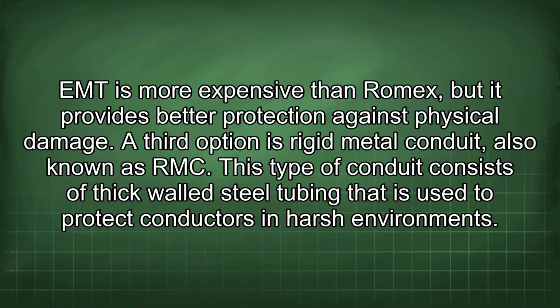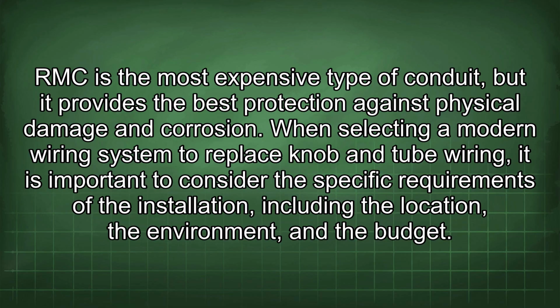A third option is rigid metal conduit, also known as RMC. This type of conduit consists of thick-walled steel tubing that is used to protect conductors in harsh environments. RMC is the most expensive type of conduit, but it provides the best protection against physical damage and corrosion.